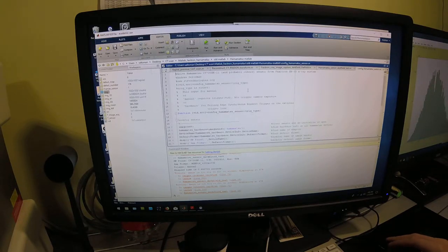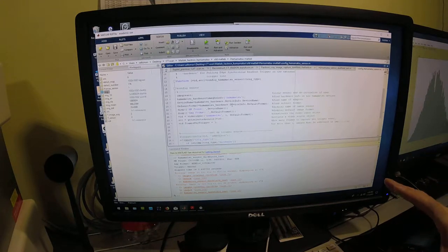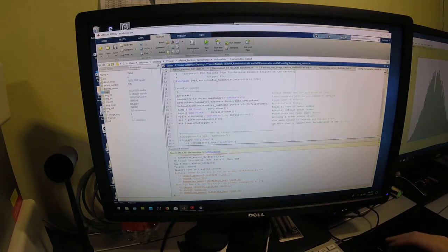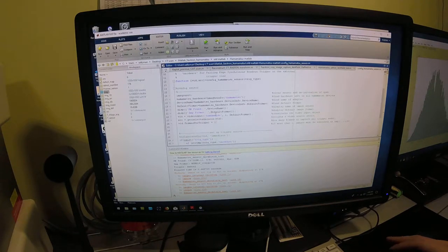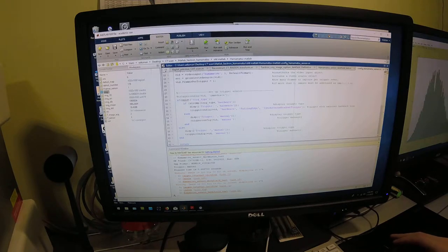So I wrote a configuration script. What this does is it looks for the imaqhwinfo hardware info under Hamamatsu devices, and that'll show the enumerated flat panel detector. If you look under your Device Manager under Windows, you also should see the Hamamatsu detector enumerated as USB devices. So after enumerating the device, it'll define a video input and a video source. It'll select one frame per trigger by default with the configuration script, and then it'll set the trigger to manual.